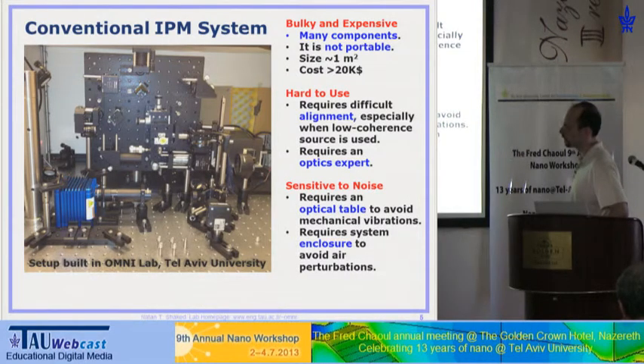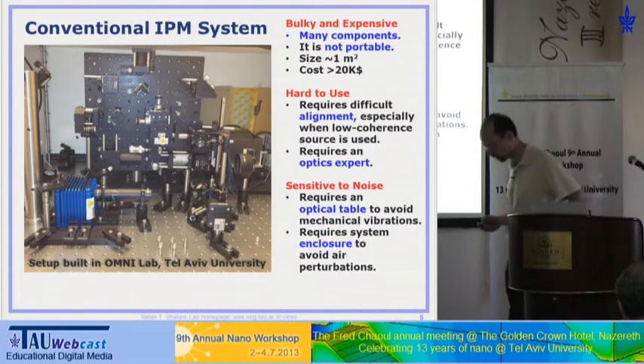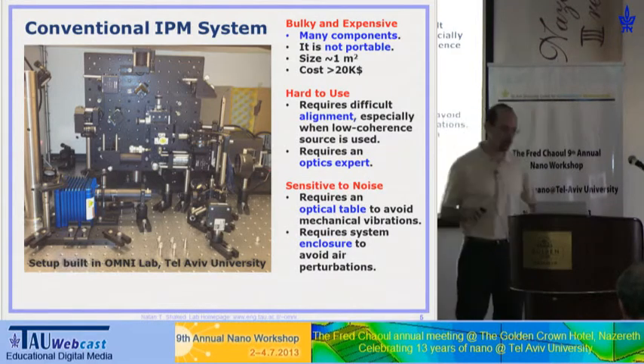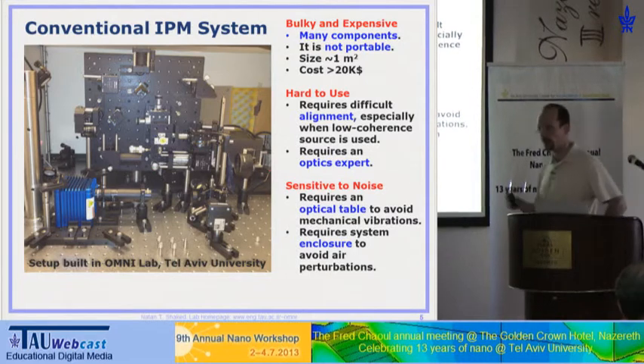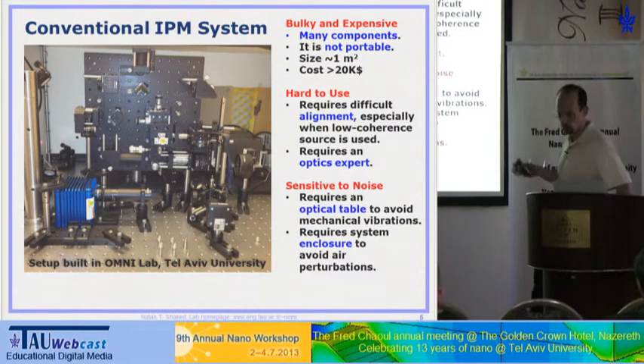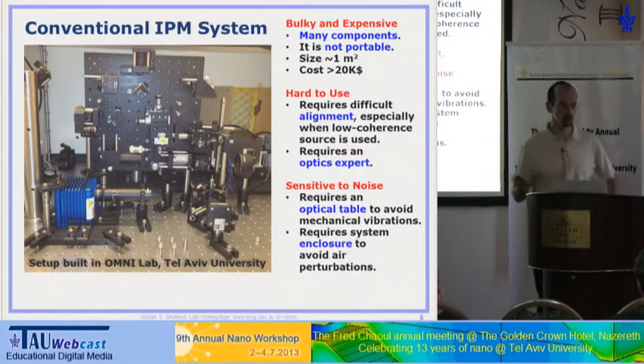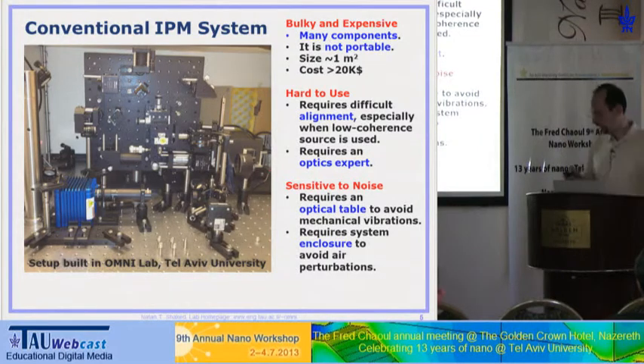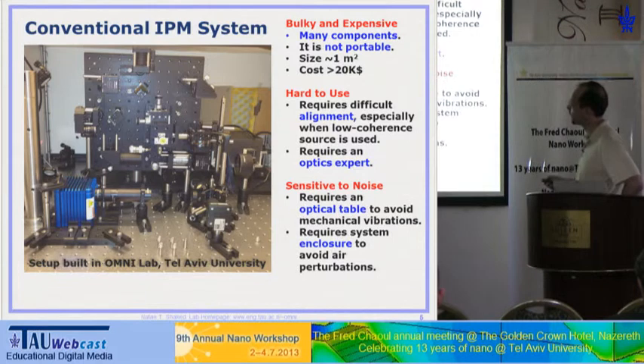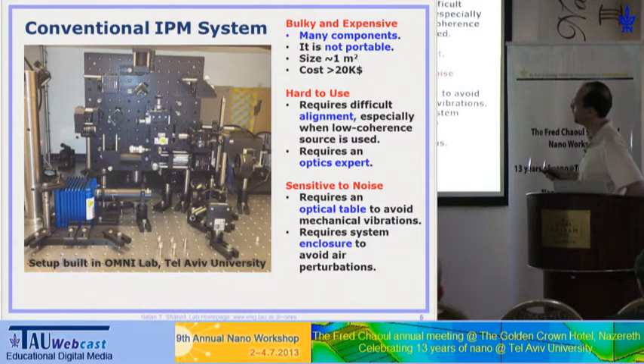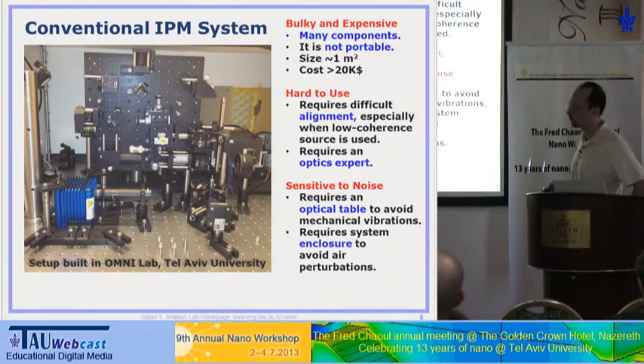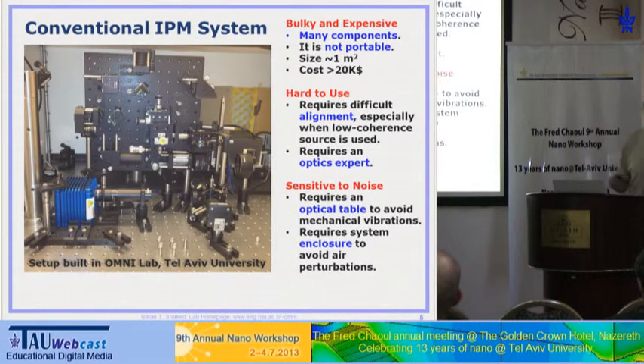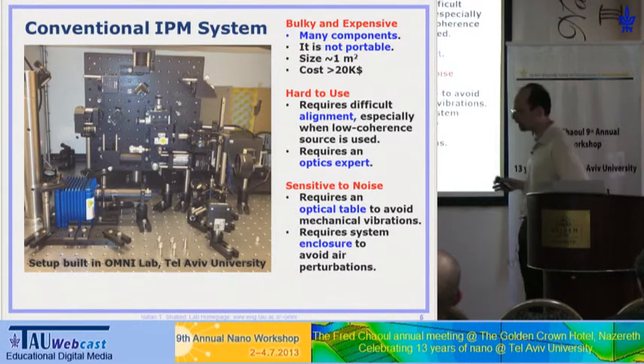We use a low-coherent laser in order to decrease coherent noise and to get sub-nanometric accuracy. Otherwise I will have spatial noise limiting the accuracy to several nanometers. This Mach-Zehnder interferometer is built vertically so I can position the sample horizontally. It has many components, it's not portable, its size is about one meter square, and its cost is more than $20,000.